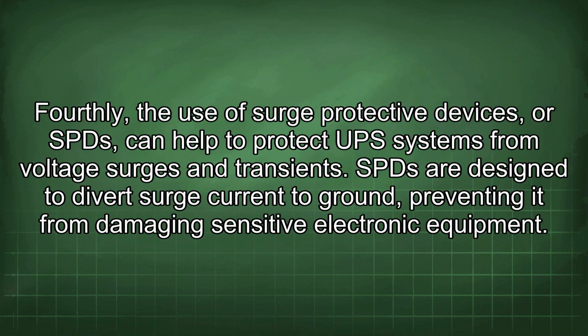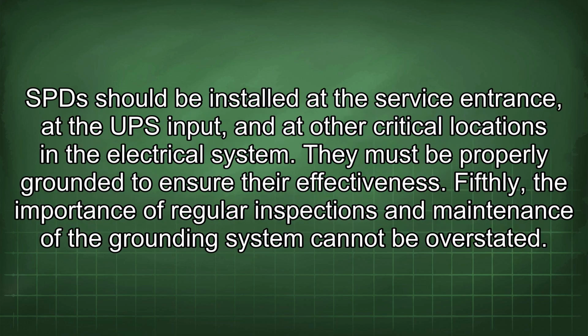Fourthly, the use of surge protective devices, or SPDs, can help to protect UPS systems from voltage surges and transients. SPDs are designed to divert surge current to ground, preventing it from damaging sensitive electronic equipment. SPDs should be installed at the service entrance, at the UPS input, and at other critical locations in the electrical system. They must be properly grounded to ensure their effectiveness.